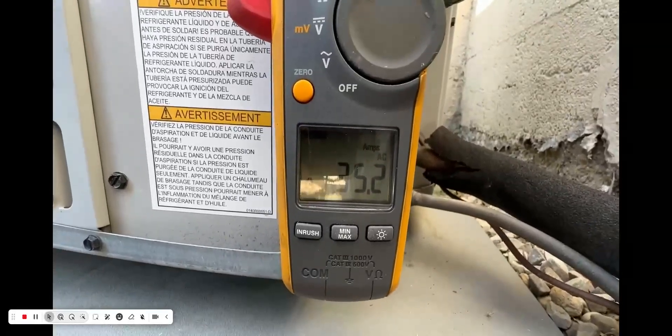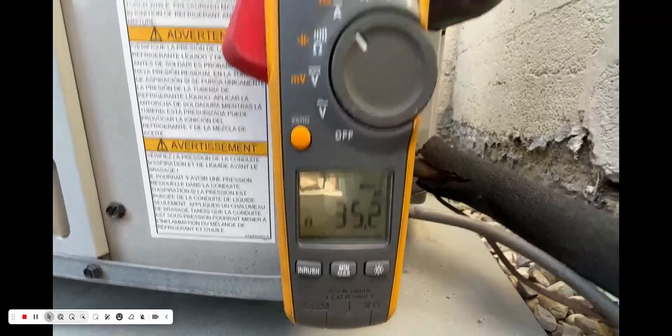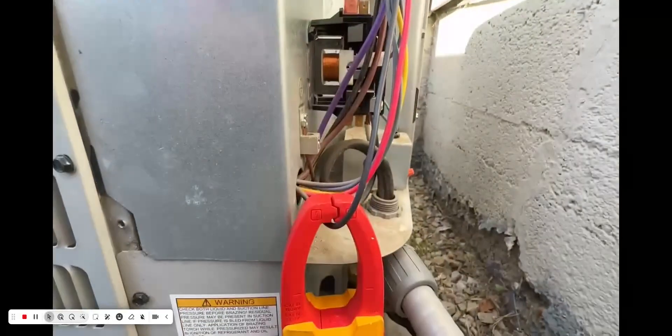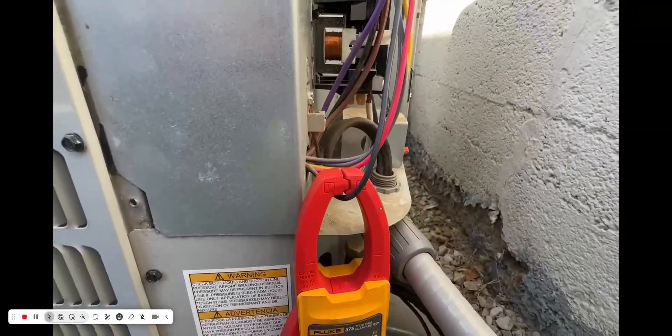Alright, so 35.2 inrush amps. This is the common wire that goes to the compressor.